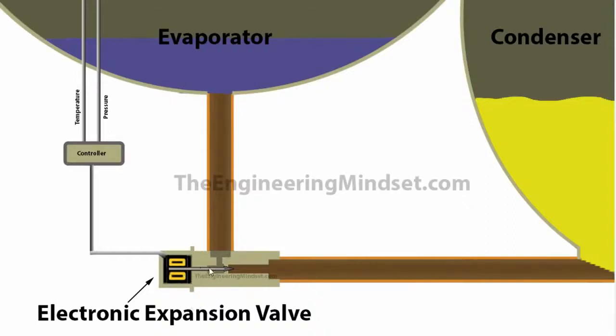So we've got the main shaft connected to the valve head inside the body there. Then behind that we've got the stepper motor, and that is connected to a controller. The controller measures the temperature and pressure from the evaporator outlet, and this allows the superheat to be calculated and that value to be determined. The controller decides is there enough superheat or not, and then sends a signal to the stepper motor to very precisely control this shaft in the valve head to move that back to allow and adjust the refrigerant flow rate.